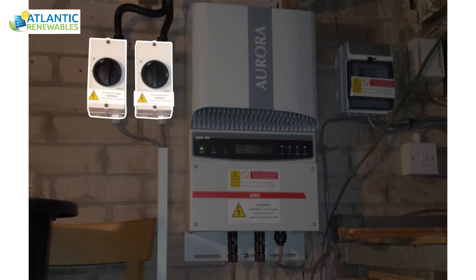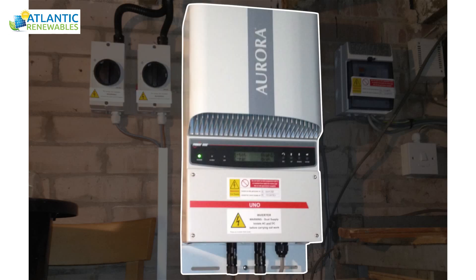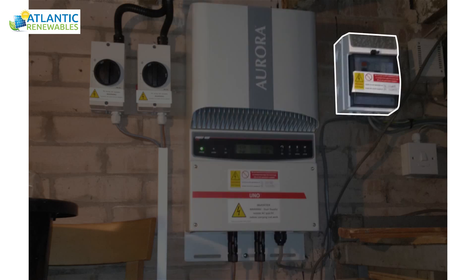These are the two DC isolating switches which isolate the incoming power from the rooftop array. This is the inverter which transforms the DC electricity produced from the solar PV array into an AC electric supply which can be used throughout the property. On the right is the RCD device which would isolate the electricity supply in the event of a fault, ensuring the overall safety of the system.